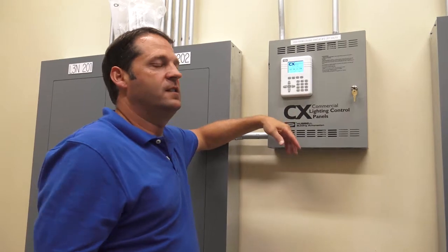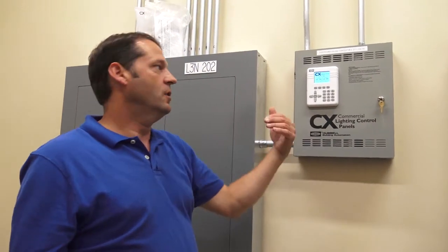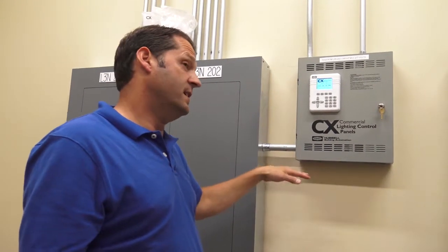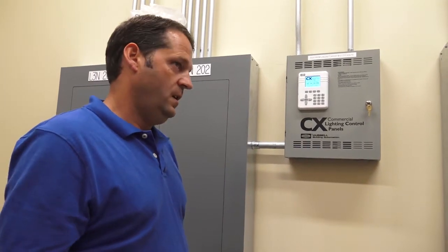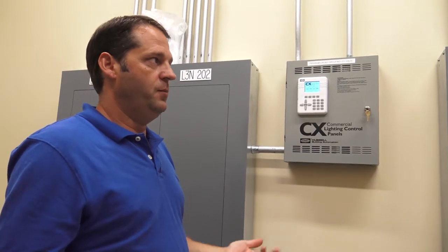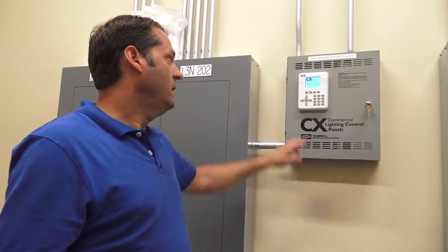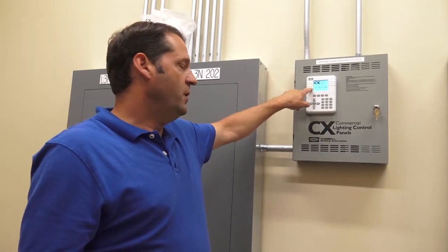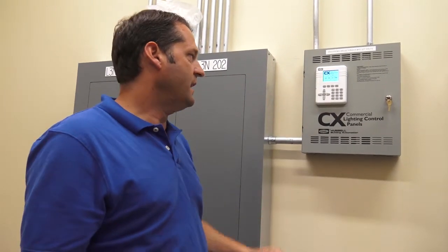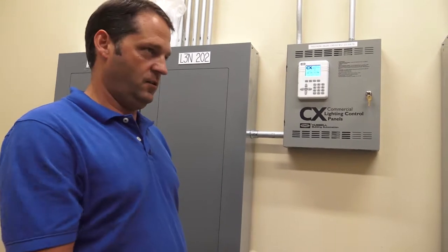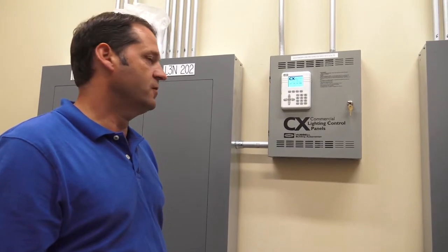And what you'll notice is if your lights are scheduled to come on at 6 a.m. up here and shut off at 8 a.m., well, they're going to come on at 6:02. And whatever time your employees are showing up, they're going to be like, hey, the lights aren't on when you're here. Well, first thing you want to do is come here and check this, see how accurate this is. Because if that clock gets out of adjustment, it's going to affect all of your schedules.